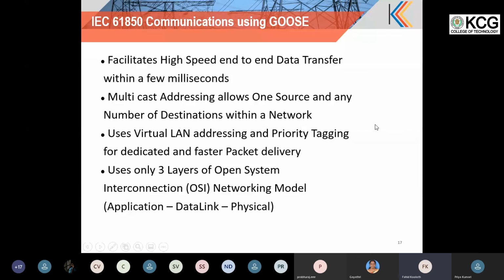Then, for example, there are hundreds of IEDs in a bay level equipment. If we send the GOOSE out, because it depends upon broadcast or multicast at the Ethernet level, every network will get congested. So in order to segregate that, we can have virtual LANs within the same physical LAN. For example, GOOSE 1 needs to be sent to 5 devices. These 5 subscribers can be put on a virtual LAN in the GOOSE transmit, so that the message will be transmitted across these devices only, and the entire network will not have the burden of getting a GOOSE which is unwanted for other devices.